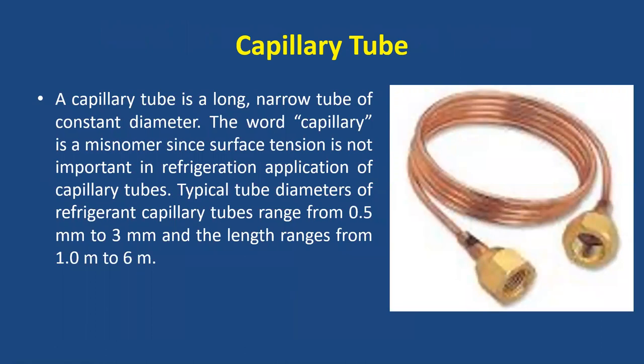A capillary tube is a long, narrow tube of constant diameter, generally used for small systems like refrigerators or small-capacity window air conditioners of 1 TR or less. Its use is complicated for larger capacities due to mass flow restrictions. A major advantage is that pressure equalization occurs before the compressor starts, allowing the use of a low starting torque electric motor.